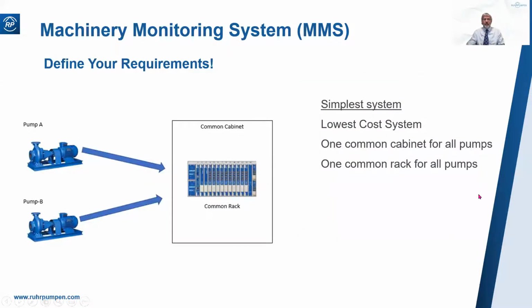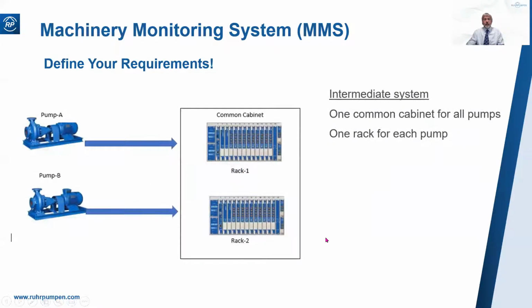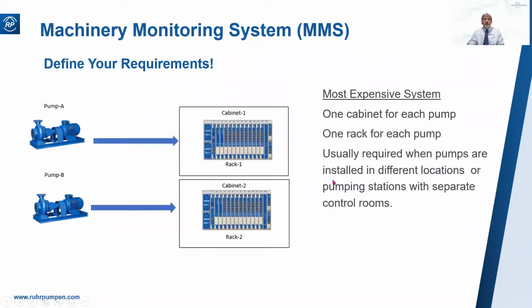So let me show you 3 scenarios. First, the simplest, lowest cost system, which is 1 cabinet, 1 common rack for all the pumps. The intermediate option has 1 cabinet in the control room, but 1 rack for each pump. Now, this is probably the most commonly specified way of doing it. And this would be the most expensive system, where you have 1 cabinet for each pump and 1 rack for each pump. This would usually be required when the pumps are installed in completely different locations or pumping stations with separate control rooms.